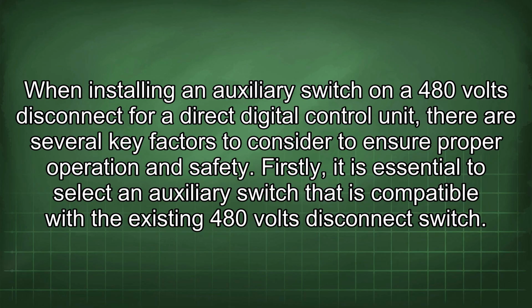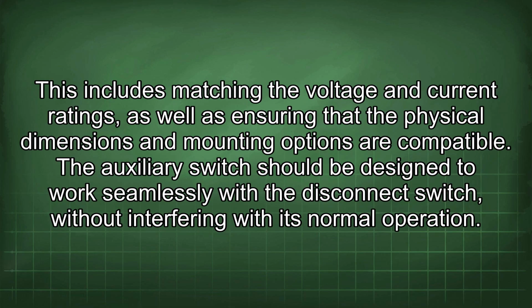When installing an auxiliary switch on a 480 volts disconnect for a direct digital control unit, there are several key factors to consider to ensure proper operation and safety. Firstly, it is essential to select an auxiliary switch that is compatible with the existing 480 volts disconnect switch. This includes matching the voltage and current ratings, as well as ensuring that the physical dimensions and mounting options are compatible. The auxiliary switch should be designed to work seamlessly with the disconnect switch, without interfering with its normal operation.